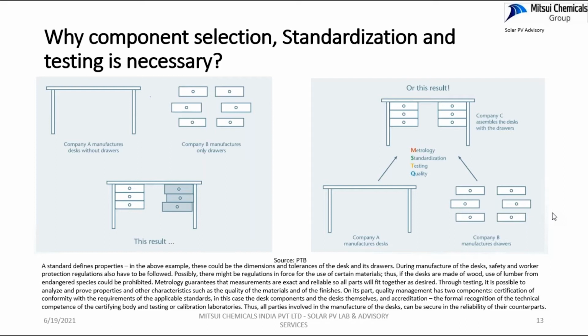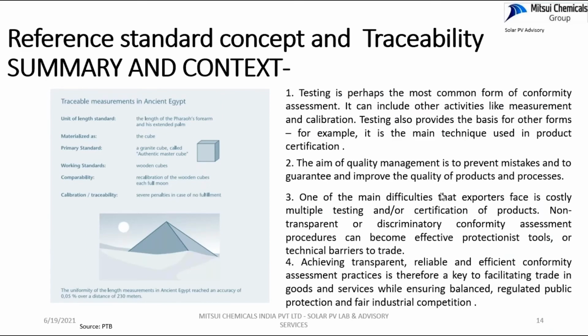This is one example. Basically, labs are just one step higher than manufacturers - we do calibrations, we maintain reference standards, and we give the reference standards. We transfer the quality to the manufacturer so they can have traceability through an unbroken chain up to the international standards.